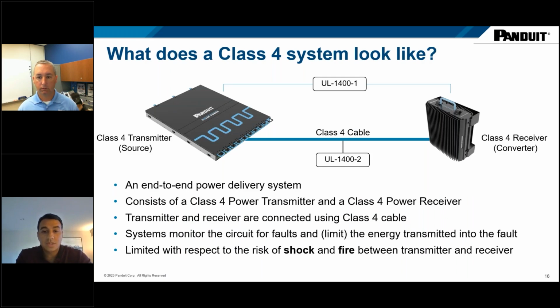So what does a class 4 system look like? Here I'm showing you an end-to-end system, and it will always comprise a transmitter or source and a receiver or converter. The converter or receiver will be somewhere remote, in a remote location trying to power devices, and they'll need to be connected by a class 4 cable. The UL 1400 standard has two parts to it: -1 covers the systems and -2 covers cable.